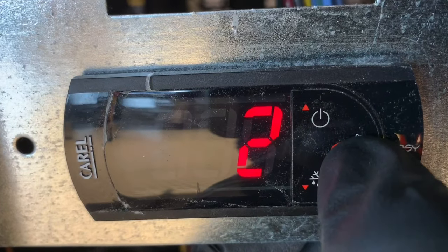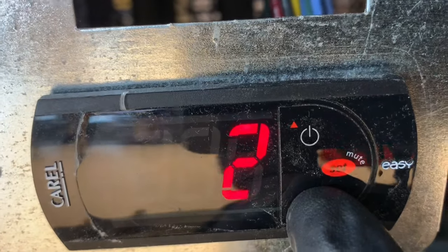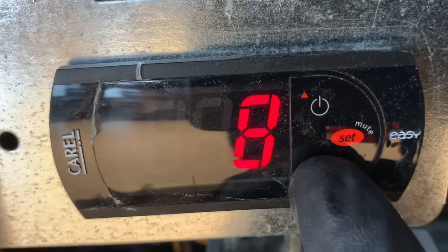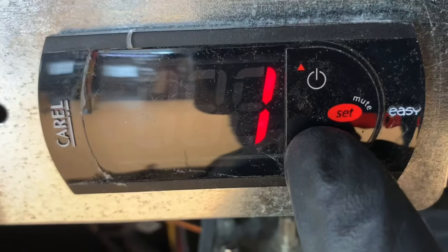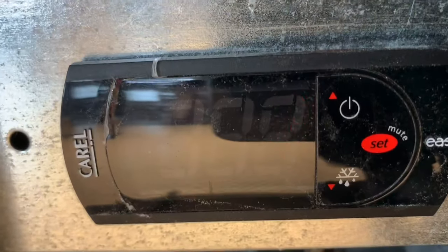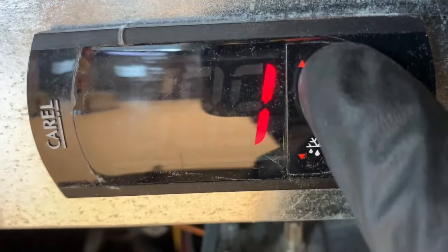Now the set points — if you hit set and hold it, this number goes from 2 to 9. Now 9 is actually the coldest set point and 1 is the warmest set point. There are a lot of increments between 9 and 1. I believe the range — the difference between 9 and 1 — is about 4 to 5 degrees.